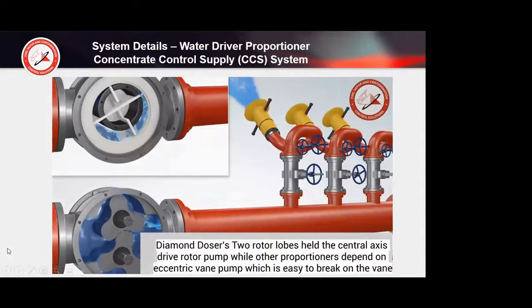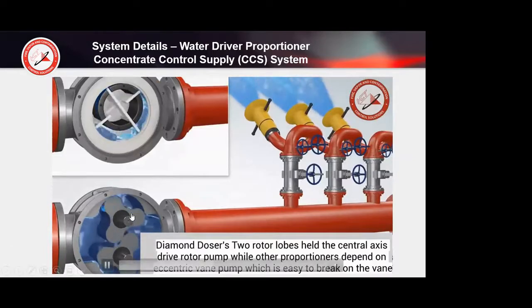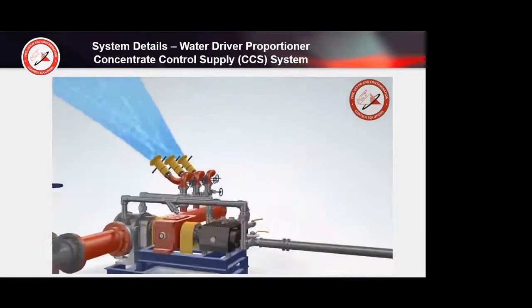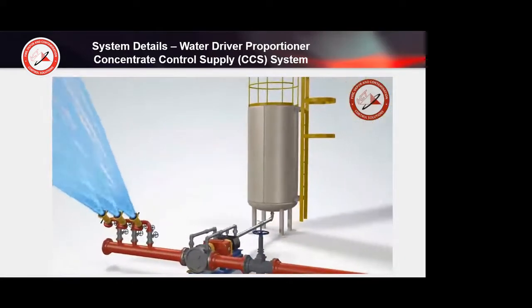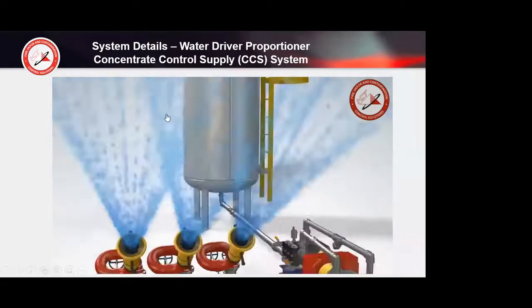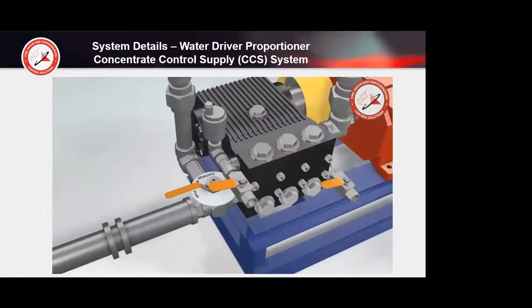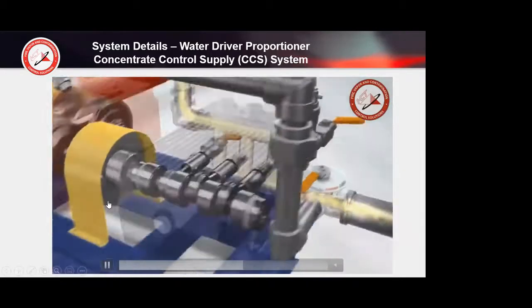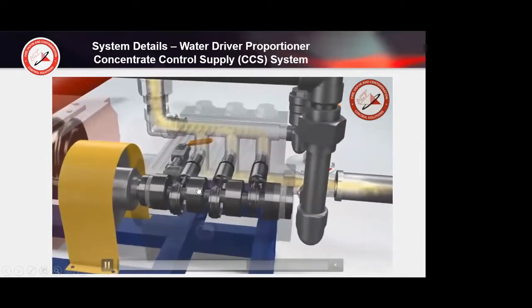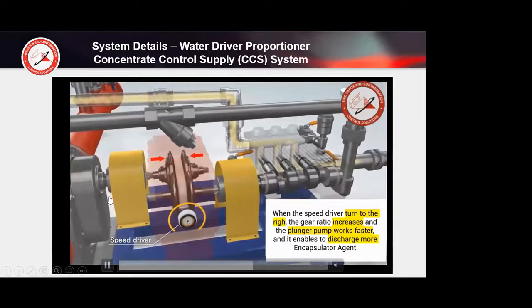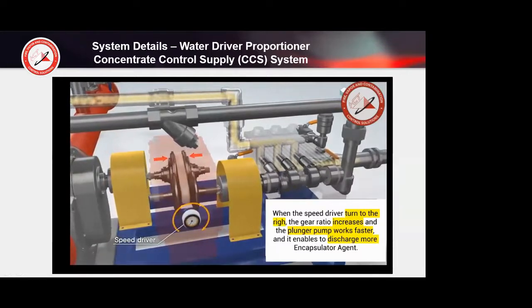So as the water is flowing through the water motor, it's turning the motor. As the water goes faster, the motor goes faster. As the water goes slower, the motor goes slower. Then you have an agent holding tank. That can usually be a plastic atmospheric tank. Open the valve, allow agent to flow through. So as the water turns the motor, it's turning these pistons, which is actually injecting the agent into the water.